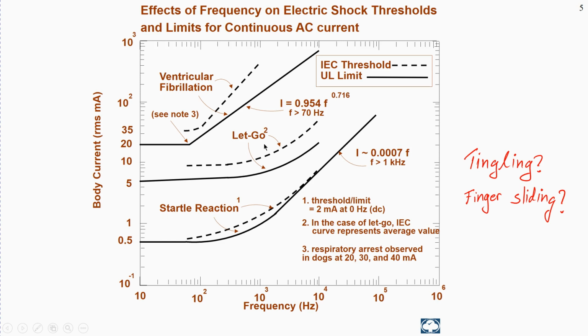'Let-go' current is when you'd like to let go of something, and this is around 5 milliamps. Then if you get to 20 milliamps, this is really the dangerous area where you can get fibrillation, a heart attack — very dangerous. So these graphs aren't really talking about the tingling or sandpaper-like sensation as you rub your finger across the casing, which occurs much below the 0.5 milliamp level.